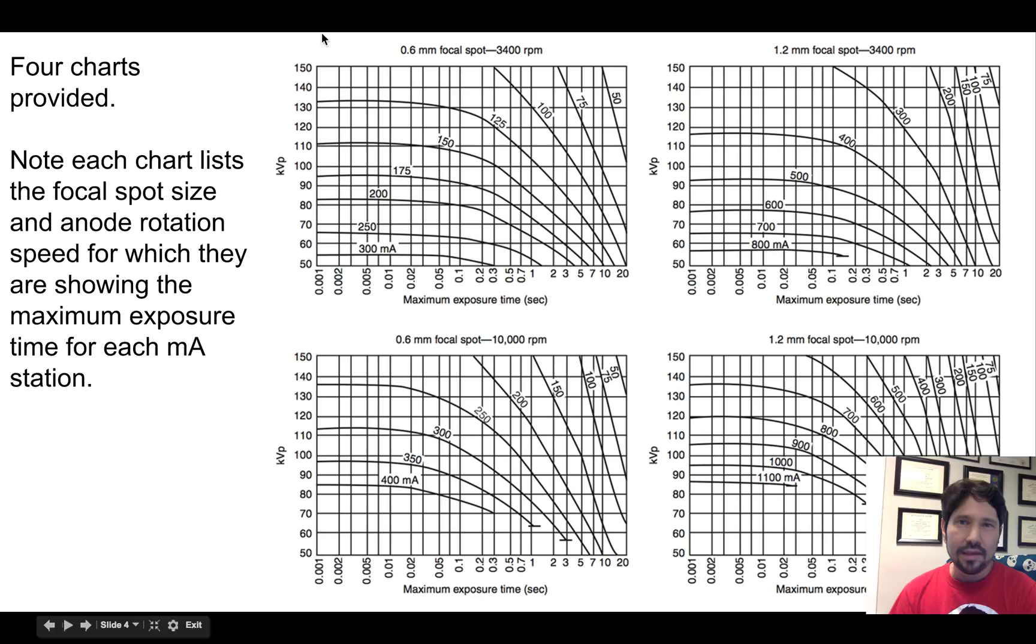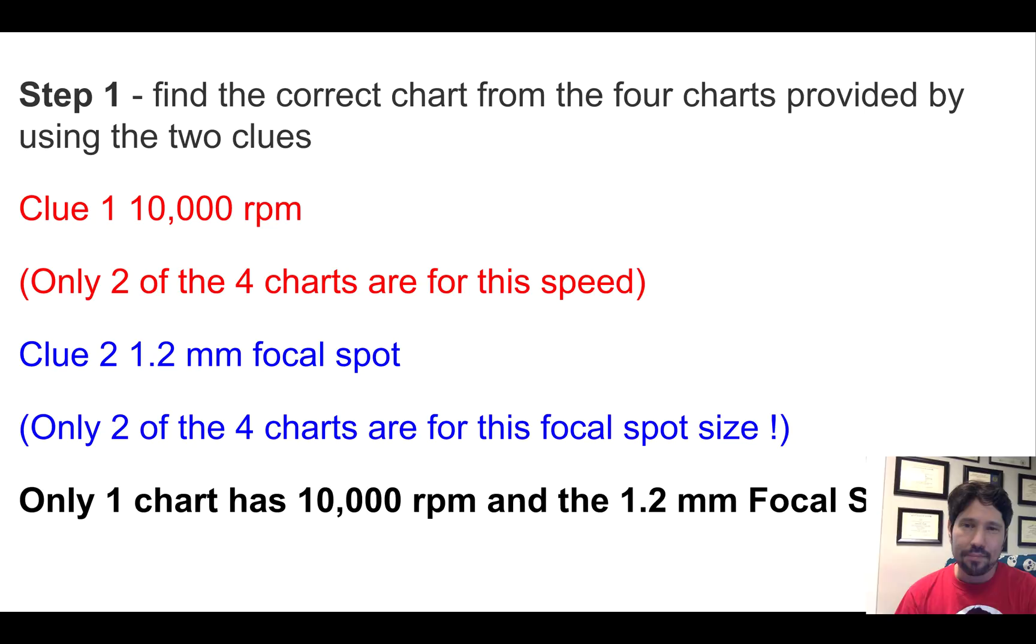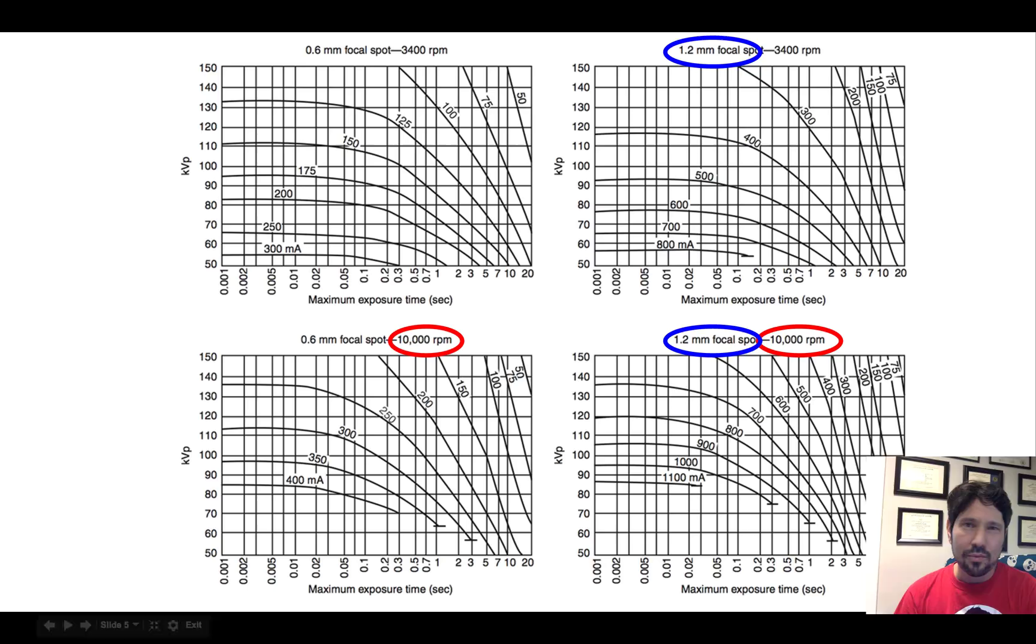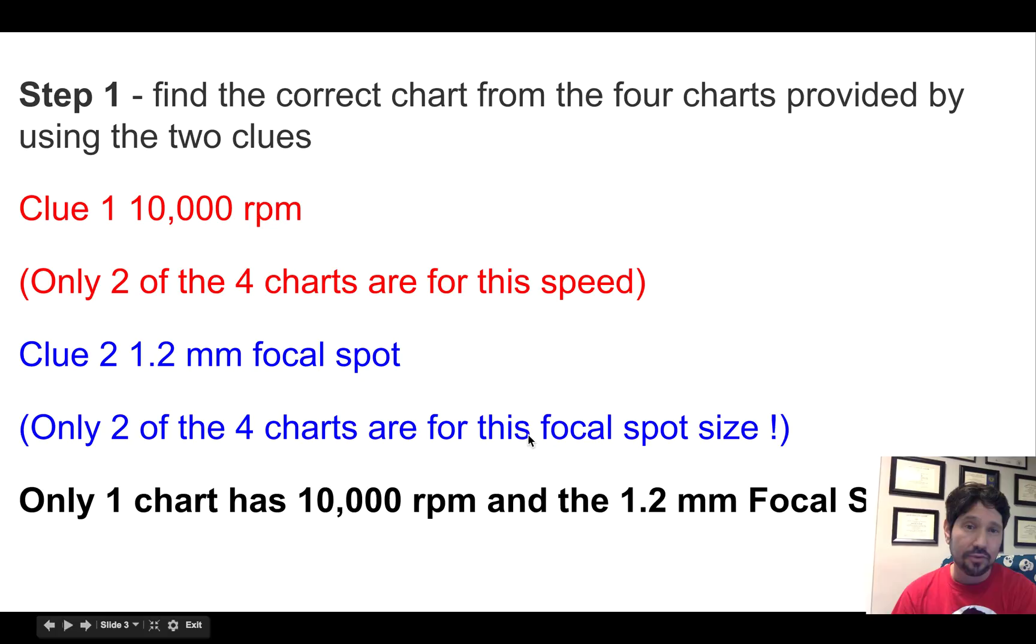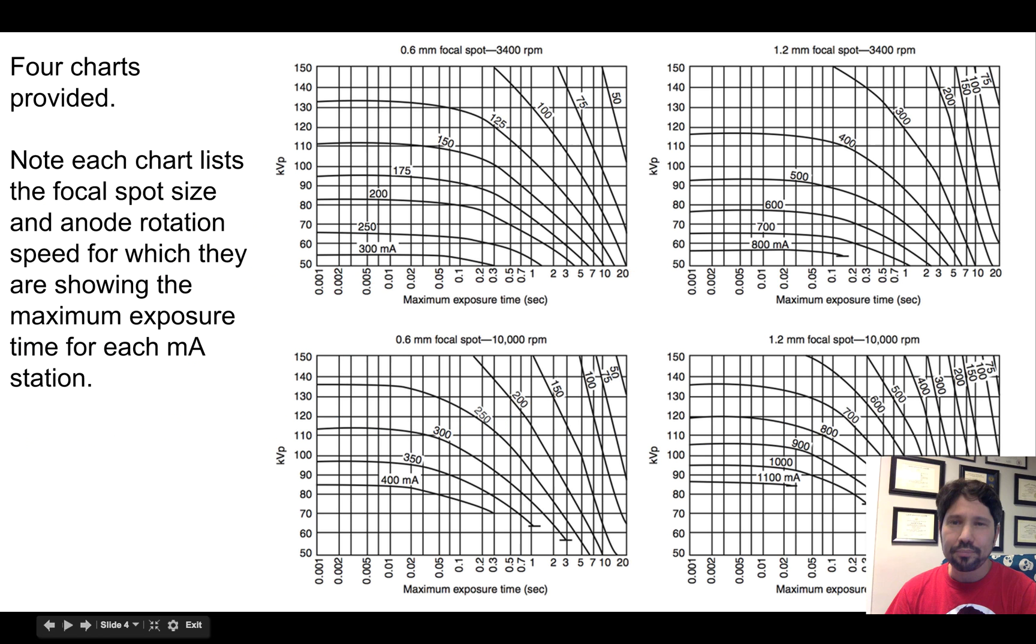So in this problem, Dr. Wuxiang gave us four charts. We can see one chart has 0.6 millimeter focal spot size and 3400 RPM. This one has that small focal spot size, but spinning faster at 10,000. Here's the large focal spot spinning at 3400, and here's the large focal spot spinning at 10,000. So we were given two charts of the four that are for a certain speed, and two of the four that are for the focal spot.